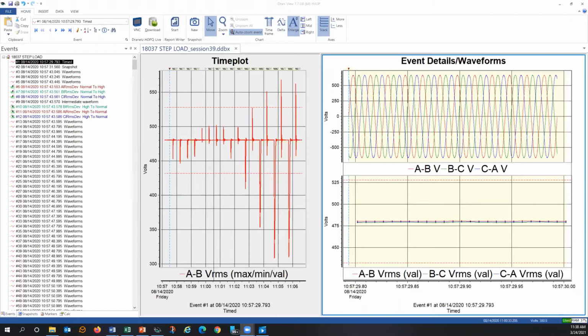recognize with that again, is that it does the one cycle calculations per 61000-4-30, but half cycle stepping means that you're looking at one cycle when you do your RMS calculations of a wave shape, but you're only advancing your one cycle window by a half a cycle. And then you do it again and again, and you have these overlapping half cycles in your computations. It's the way 61000-4-30 Class A defines how to work.